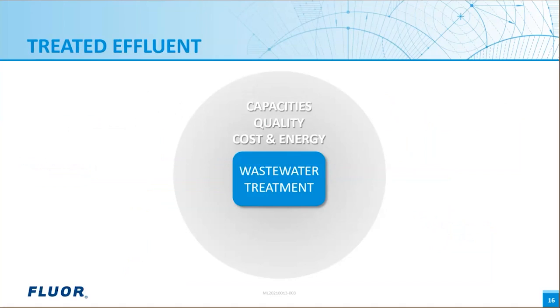Treated wastewater destinations look similar to treated water sources. Surface discharge will typically be the least flow constrained destination, but will have the most stringently controlled effluent quality. Ocean discharges are typically less stringent, but will be region dependent. It's worth noting that compositions can be regulated by end of pipe composition or the relative effect on receiving stream at the edge of the dispersion zone.